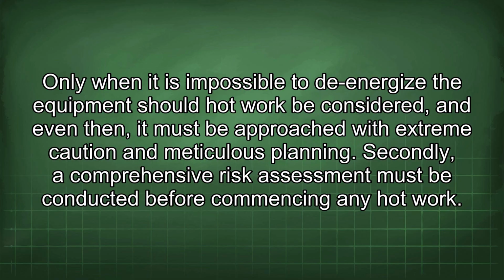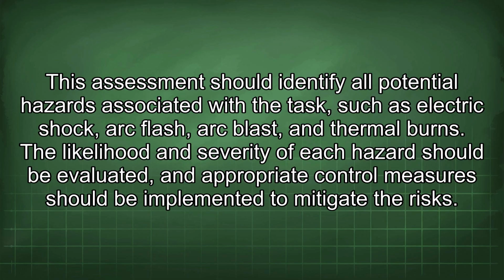Secondly, a comprehensive risk assessment must be conducted before commencing any hot work. This assessment should identify all potential hazards associated with the task, such as electric shock, arc flash, arc blast, and thermal burns. The likelihood and severity of each hazard should be evaluated, and appropriate control measures should be implemented to mitigate the risks.